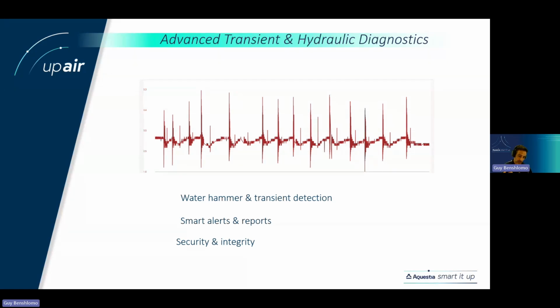And when working with the application engineers that we have in Aquestia and analyzing the situation, we gave them two pieces of advice. They have bladder tanks there that are supposed to reduce this water hammer. First, we told them to calibrate the bladder tank so they will avoid those issues. And the second solution that we gave them is putting in a hydraulic control valve for the pumping station that will close slowly at the end when the pump stops, avoiding this water hammer. And actually, it got into their work plan and they will commission it according to their timeline.